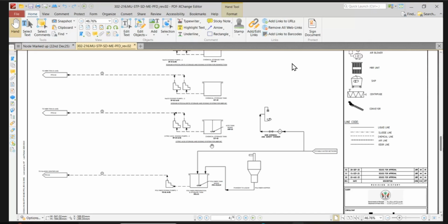SAS and RAS? Yeah, the SAS is for discharging the solids, the sludge, outside for disposal. RAS is to be sent back for treatment, again, recirculation. They are designed to maintain the biomass. Because if you are not recirculating, then with the flow, your tank doesn't have any biomass. So to maintain the biomass, based on the design, a part of the sludge will be recirculated to the inlet of the biological system, to maintain the biomass in the system.